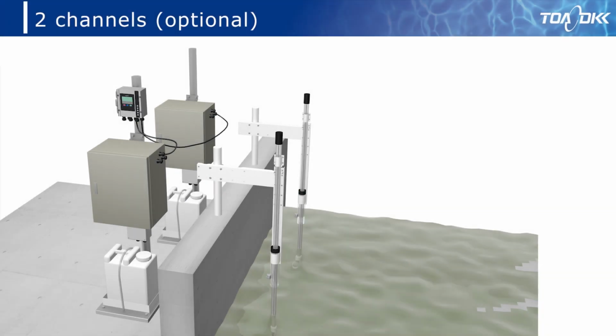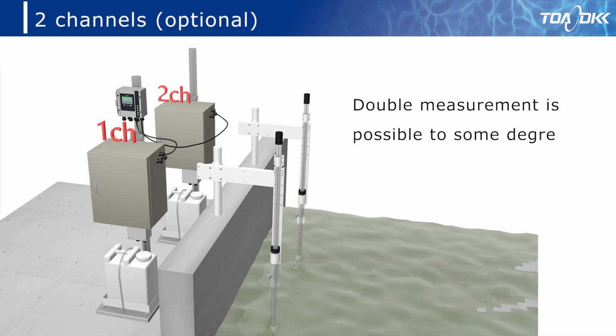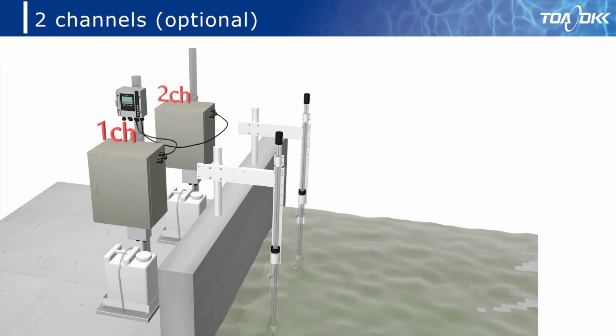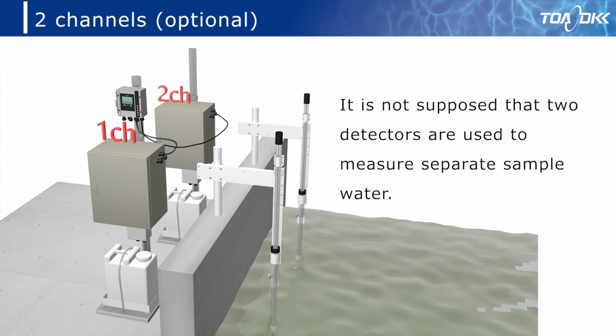This section introduces new features of the 2CH specifications as an option. As an option, 2 sets of electrodes can be connected to a transmitter. Measurement of the sample water in the same tank with 2 detectors enables double measurement to some extent. Here are 2 functions using 2-channel measurements. It is not supposed that 2 detectors are used to measure separate sample water.